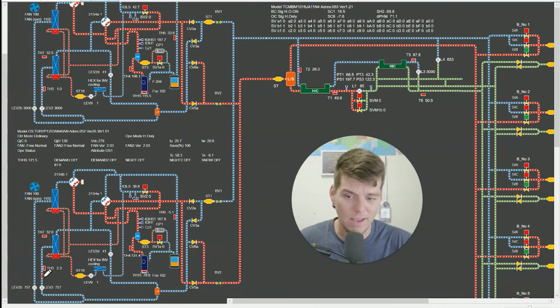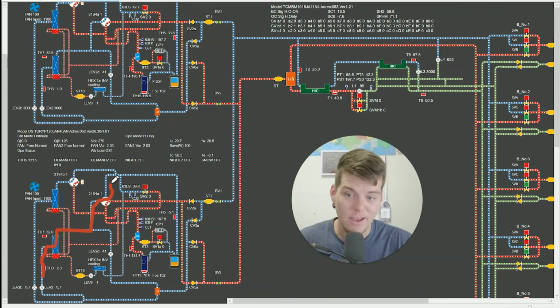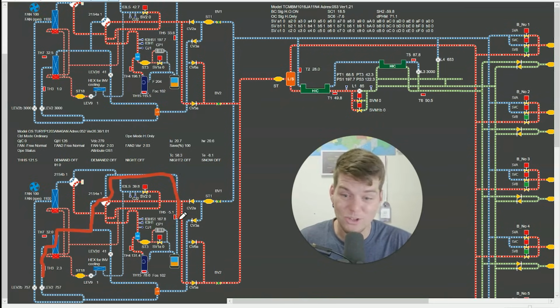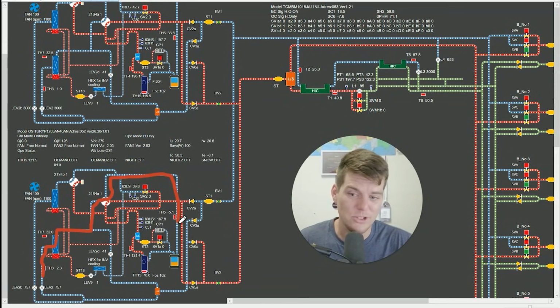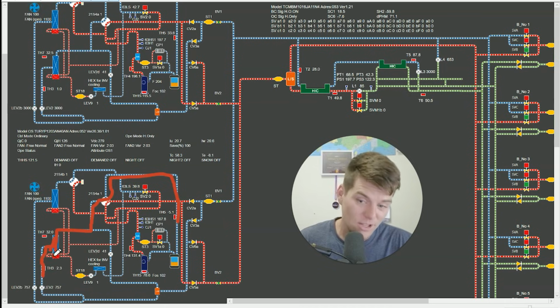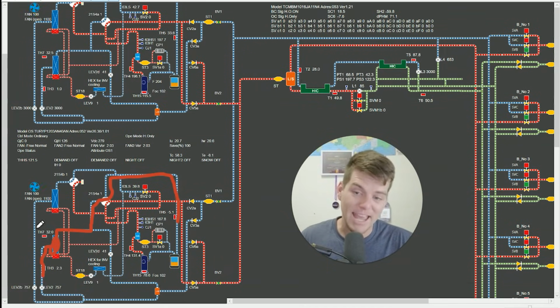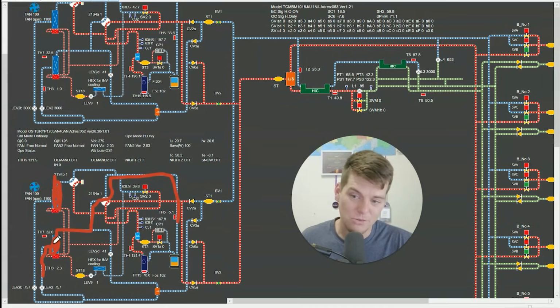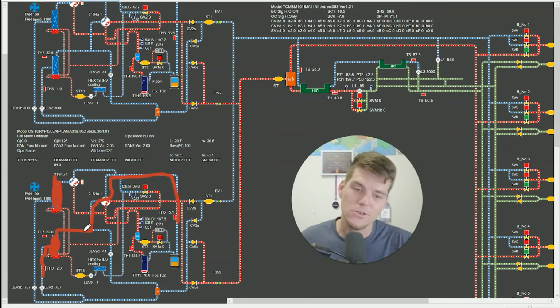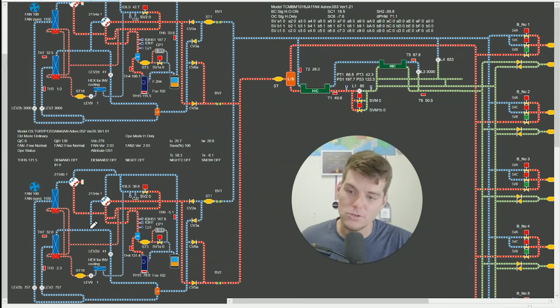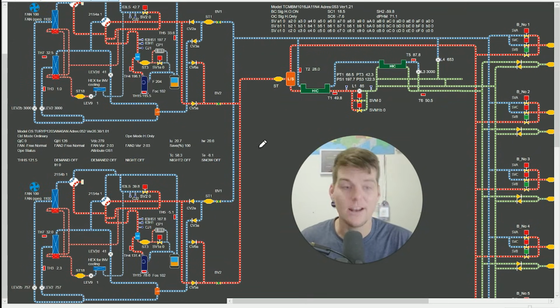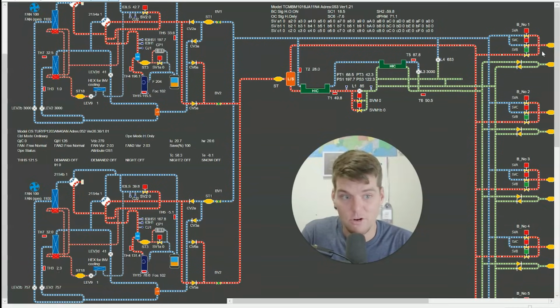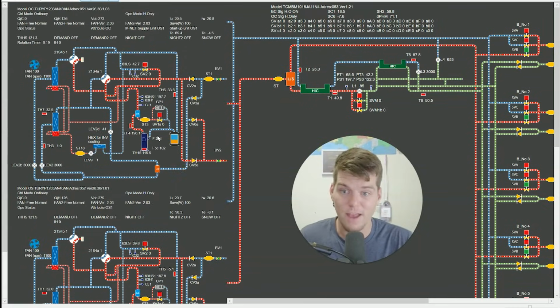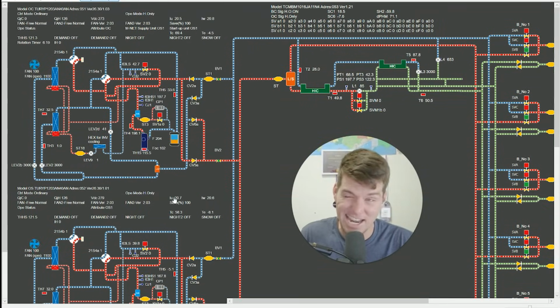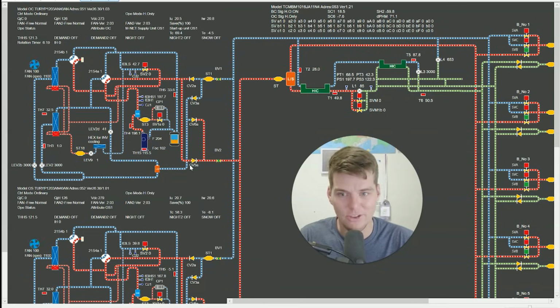So it looks like we have superheat here, but the problem is it's probably just so much liquid flowing through here that by the time it gets to here, it starts to boil off and we get 2 degrees superheat. That means that this coil is also flooded, which again, this one's stacking all the charge from the system, this one being flooded. These are two key indications that something is wrong and that the four-way valves should be checked. Now, it doesn't help that this series of equipment has notable issues where they found that the four-way valves 99% of the time usually have failed on this type of equipment.